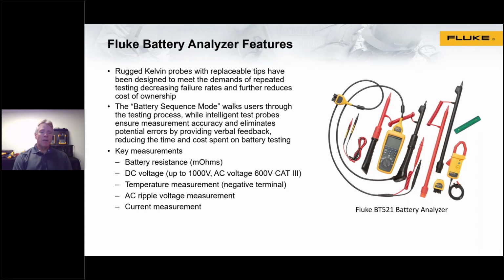It's able to make all the AC and DC measurements that you need to make. If you recall, we said that a temperature reading on the negative battery terminal is useful to look at over time. This actually has a built-in infrared sensor that will capture that negative terminal temperature. And for testing the charging systems, AC ripple voltage was a very important measurement to make, as well as current measurements. And all the accessories are included to make all the measurements that you need to make.